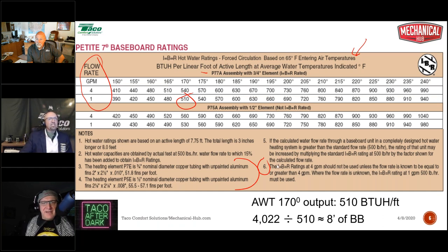Absolutely. That's the old-fashioned way of installing baseboard, of sizing baseboard. You measure the outside wall. That's step one. Step two: install that much baseboard. Now, they make it, so why not put it in, right? Hey, they're not going to be cold on my watch, so let's just load that room up. So there you've got 35 feet of baseboard where at 180 degree supply water temperature, you only needed 8. Well, hello, what does this do? What can we make of this?